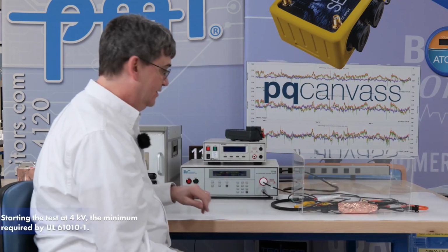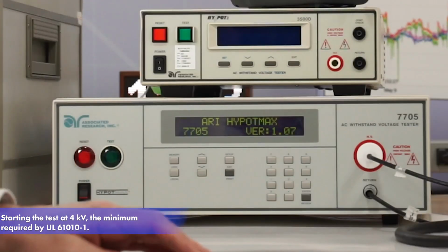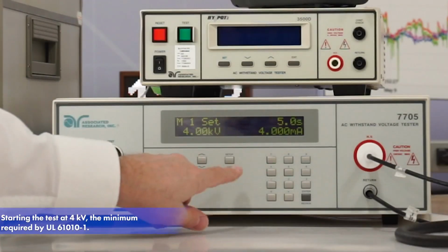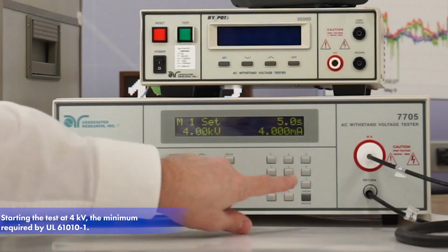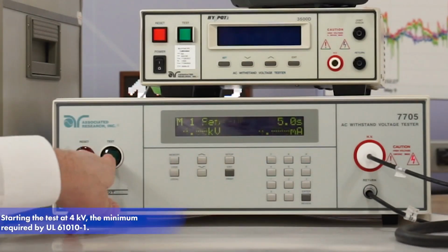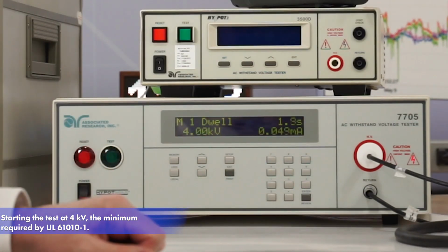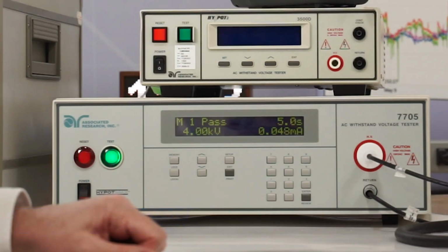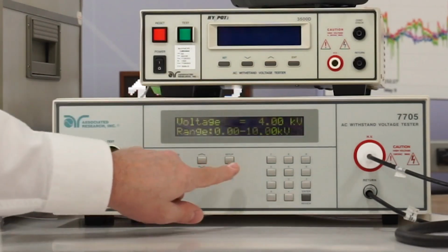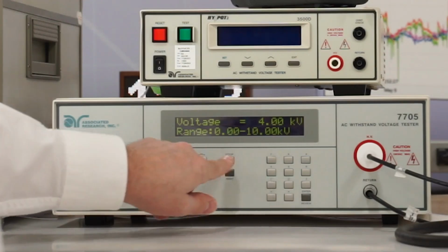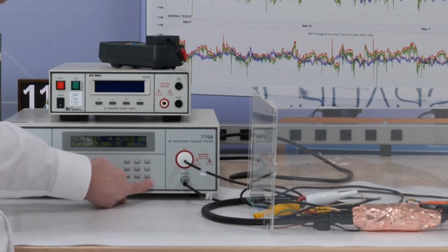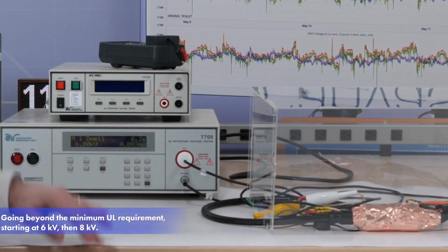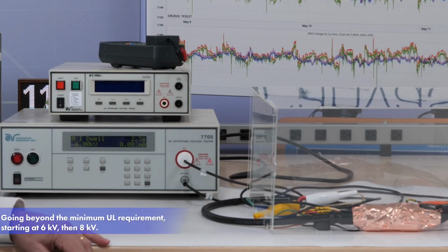So we're going to start at 4 kV, the UL minimum requirement, for 5 seconds, and we're allowed 0.5 milliamp of leakage current. And we easily pass at 48 microamps. Let's go beyond the minimum to 6 kV. And we easily pass at 80 microamps.